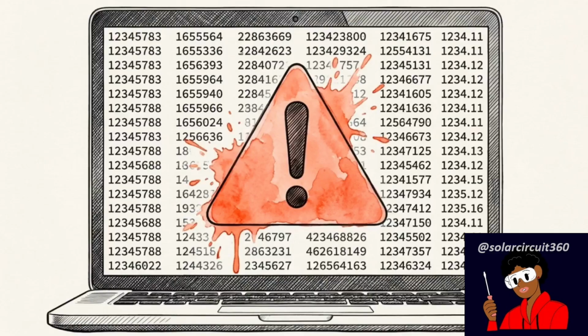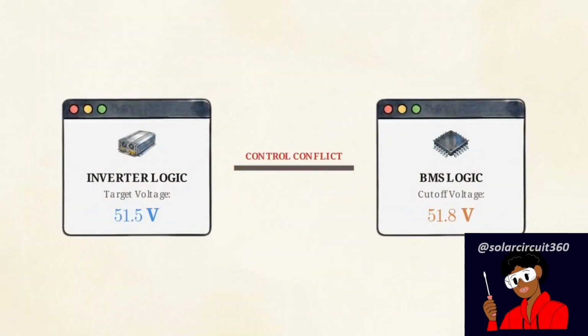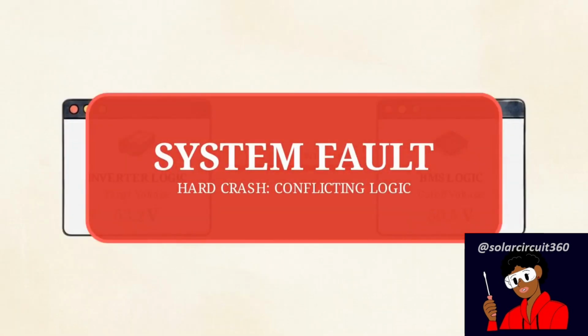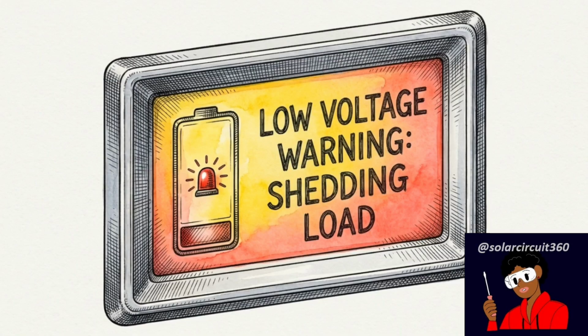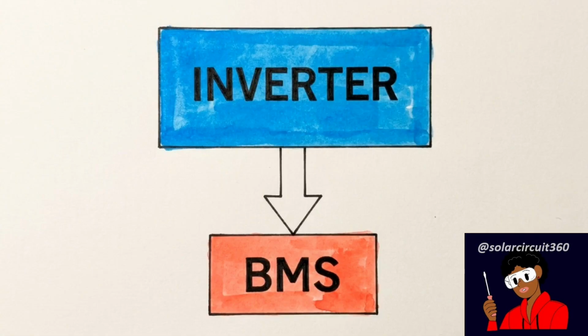If you leave them on default settings, they enter a race condition. Both controllers try to manage voltage thresholds simultaneously, resulting in hard system crashes. To guarantee backup reliability, the inverter software settings must be configured as a preemptive control layer. It has to act before the BMS ever needs to execute an emergency disconnection. System design requires establishing a clear hierarchy of rules between these two microcontrollers.